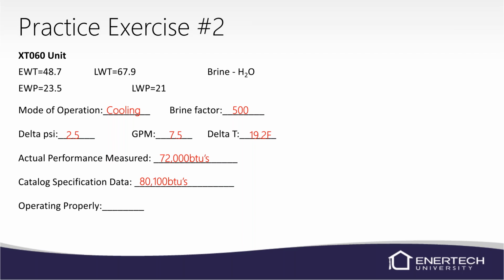So 10% of 80,000, even if it's 100, let's just say, would be 8,010 BTUs. So really, we are within 10% on this unit. We're right on the edge. In my recommendation, I would probably look back. If this is the first time you've been out there, you may want to just make a note on this unit that it's right at the 10% and to recheck it when you come back out. If you're there because they say the unit's not keeping up, you may want to dig into it a little bit deeper. But if you're just there for a service, I really would just make a note and say, make sure we check our rejection the next time we're out and make sure it hasn't dropped further down.